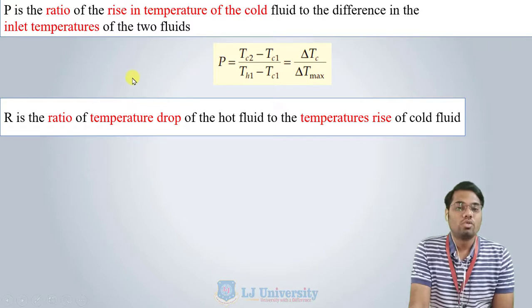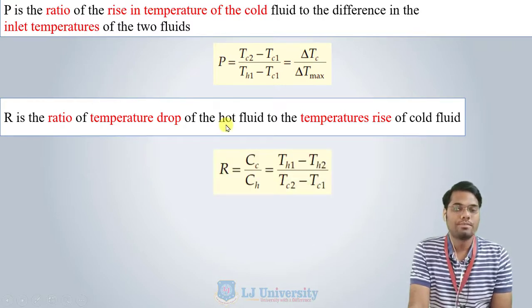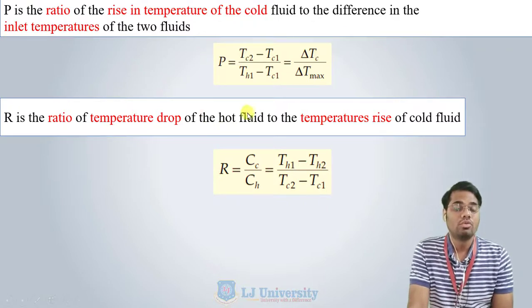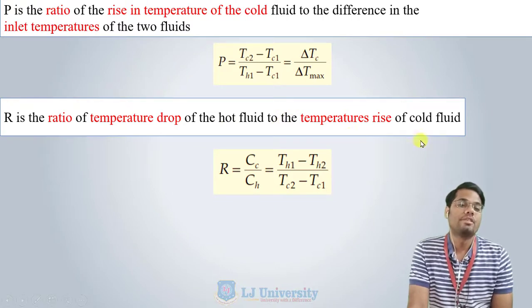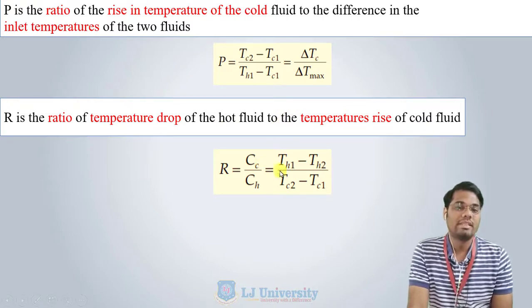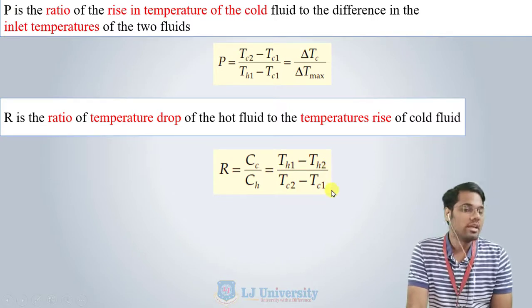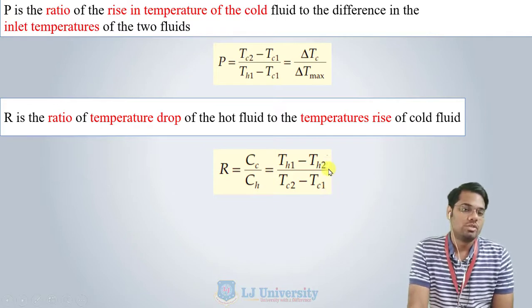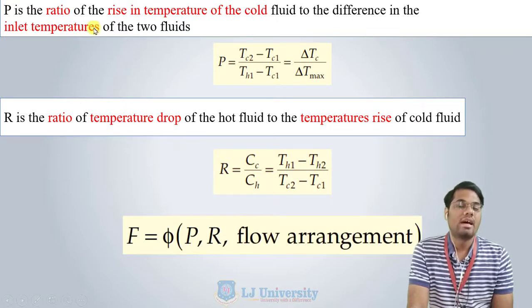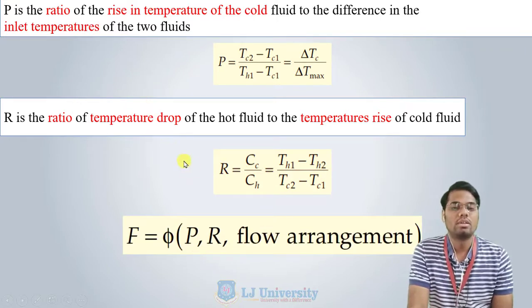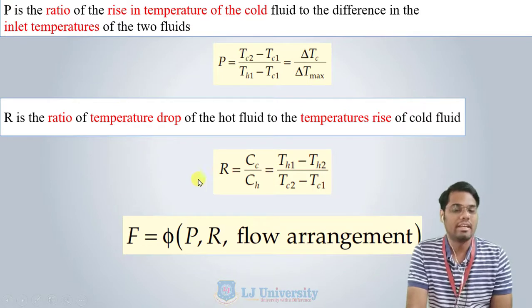R is the ratio of the temperature drop of the hot fluid to the temperature rise of the cold fluid. Since the hot fluid loses heat to the cold fluid, R = (TH1 − TH2) / (TC2 − TC1), where TH1 − TH2 is the temperature drop of the hot fluid and TC2 − TC1 is the temperature rise of the cold fluid.